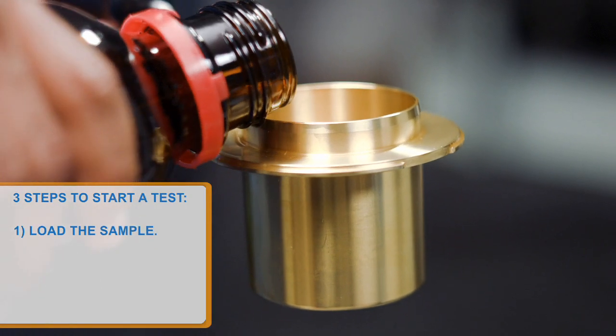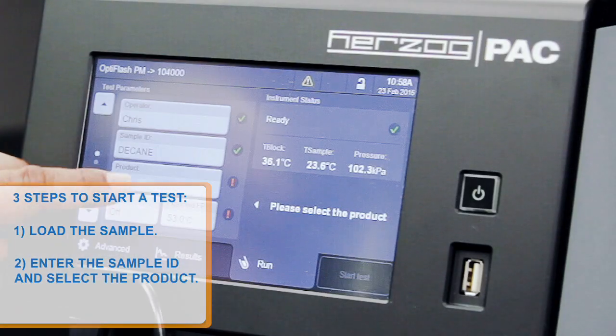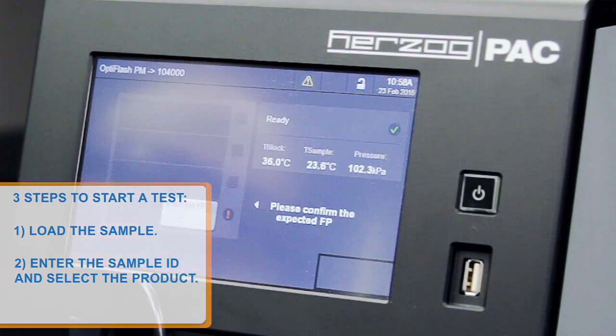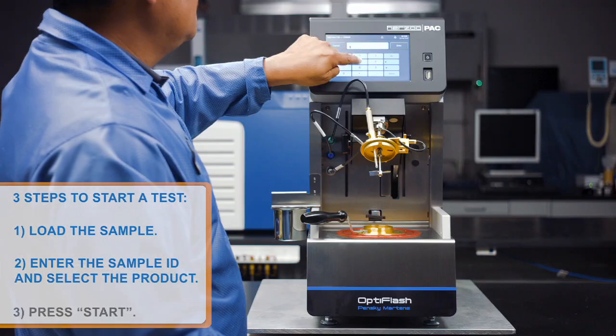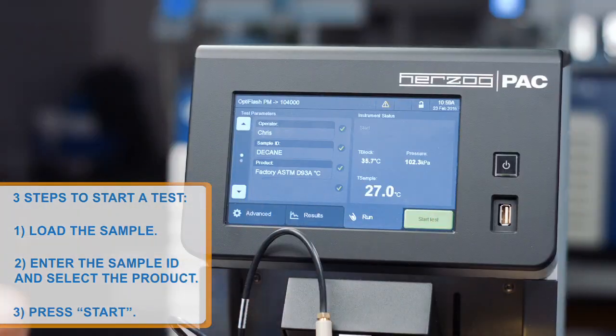One, technicians load the sample. Two, the user enters the sample ID and selects the product with the expected flashpoint. Three, all that is left is for the technician to press Start.